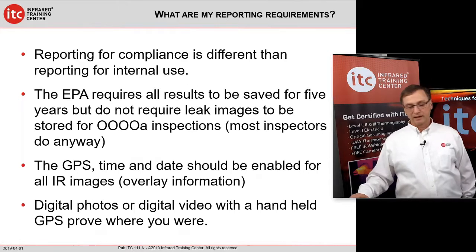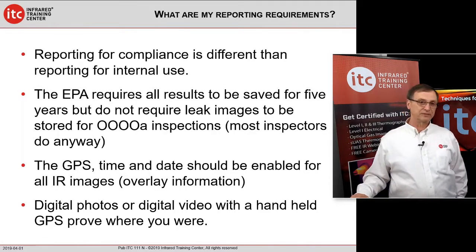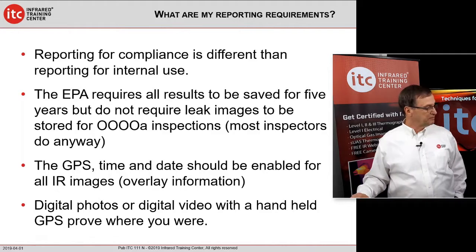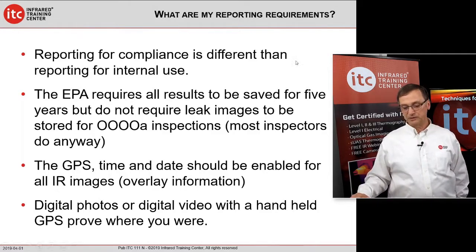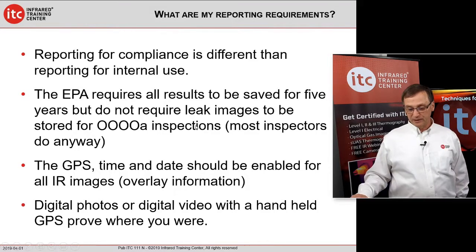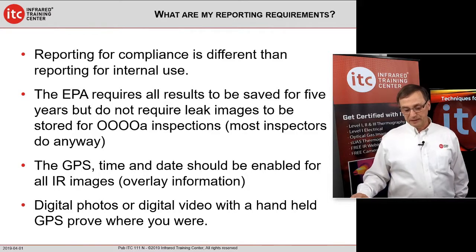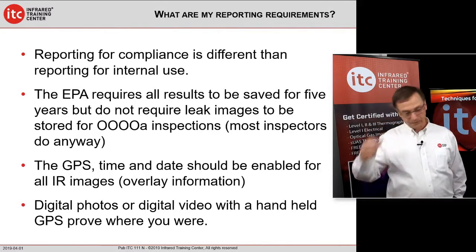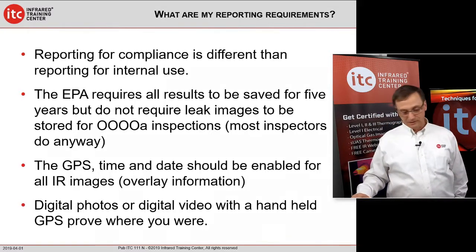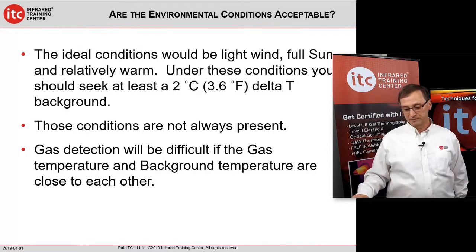What am I reporting for compliance? Reporting for compliance is different than for internal use, and that would be determined by the health and safety and legal departments as to what you have for compliance. The EPA requires all results to be saved for 5 years, but doesn't require leak images to be stored for the Quad OA inspections, although in last week's class, everybody stores them, and they're all storing the videos. And they just thought it was a great idea. And you should enable the GPS time and date for your infrared images, and also your digital photos. Not a bad idea to have a handheld GPS with you just to prove where you were.